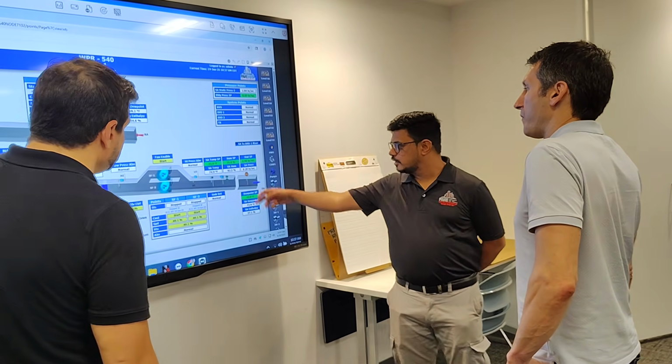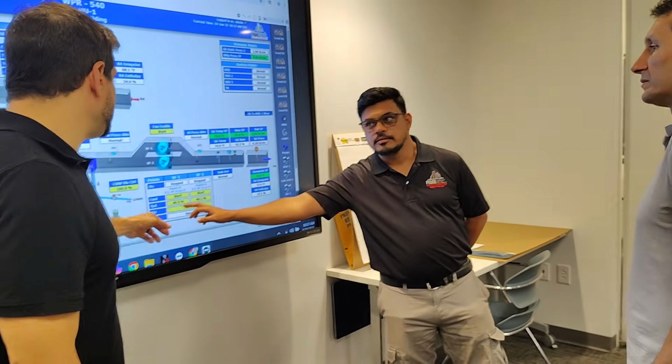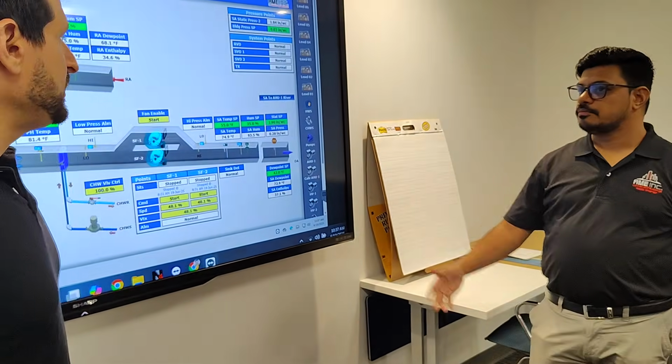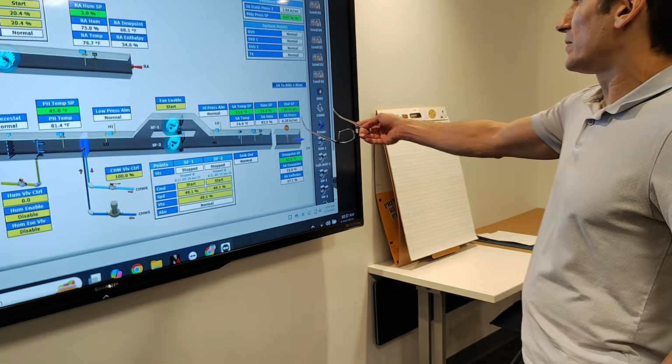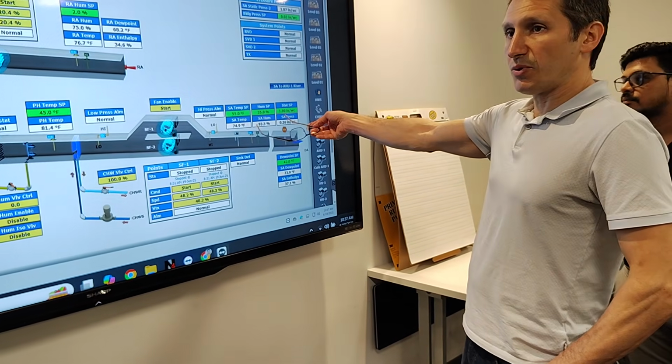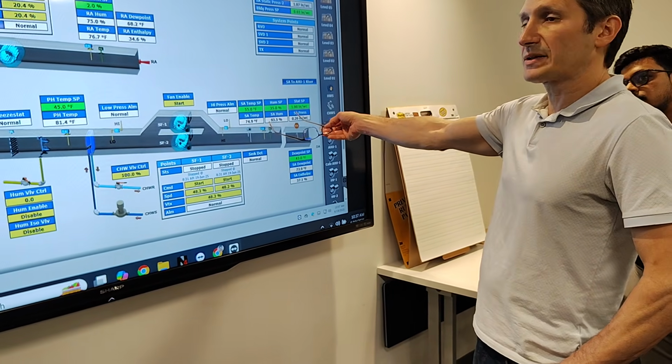Because right now it's 1.9, it should at least be at 90%. I mean, this thing hasn't even made it to halfway yet. Halfway. And it's got to be 20 minutes ago we did this. But this should be 0.9? What would be your correct set point?